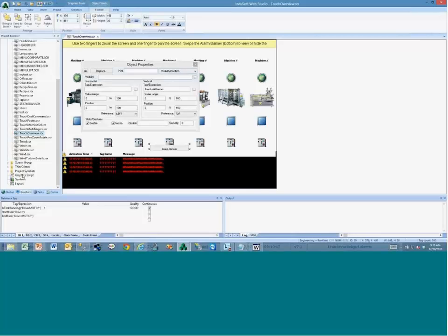So every time a thin client logs in a user, we write to a server tag, which is an array tag for the number of thin clients you have. So if you have like 20 thin clients, you create a string array with 20 positions. It must be a server tag. Whenever a thin client logs in, you look at this array, and whatever array position is empty, that thin client writes to the empty array position the name of the user logged on that station, and sets a local tag that I usually call local ID with the array position for that particular thin client.